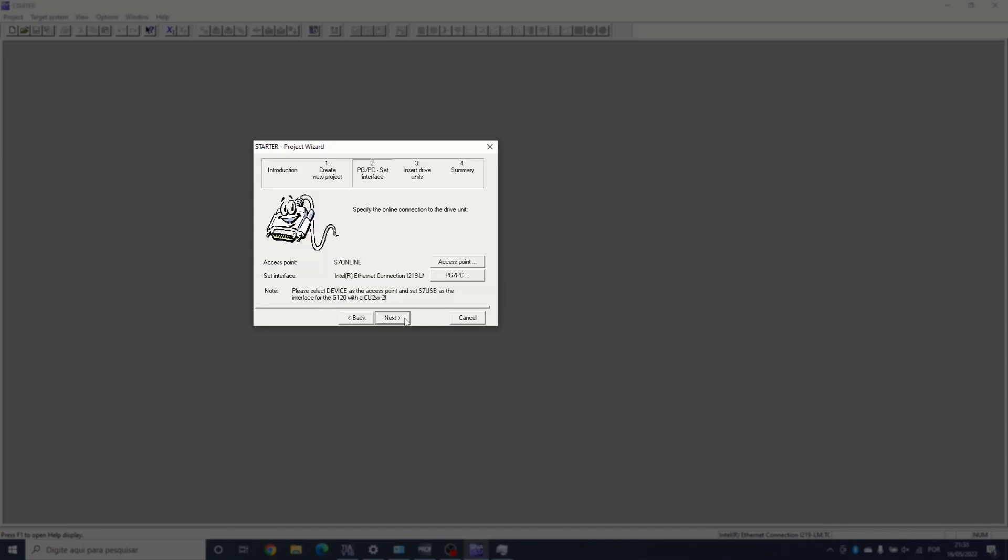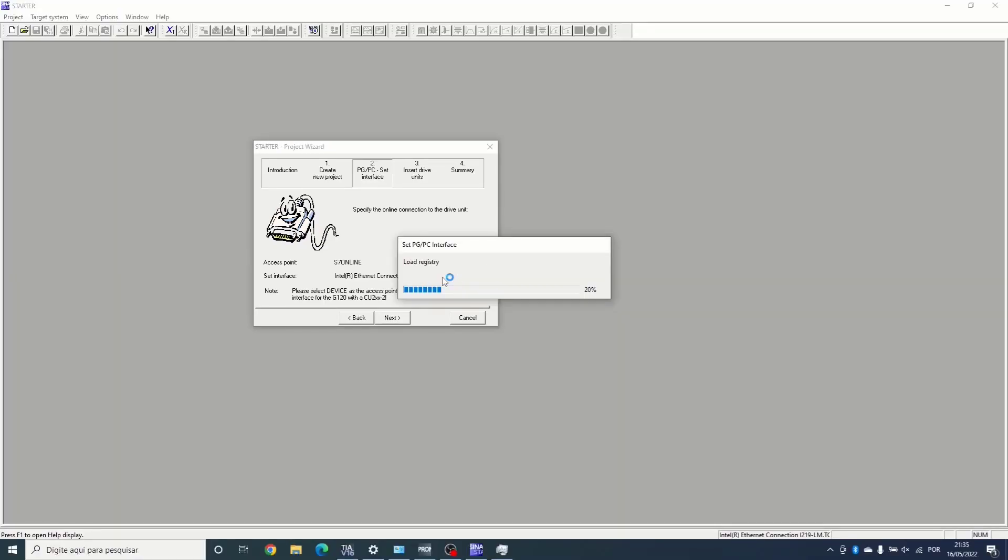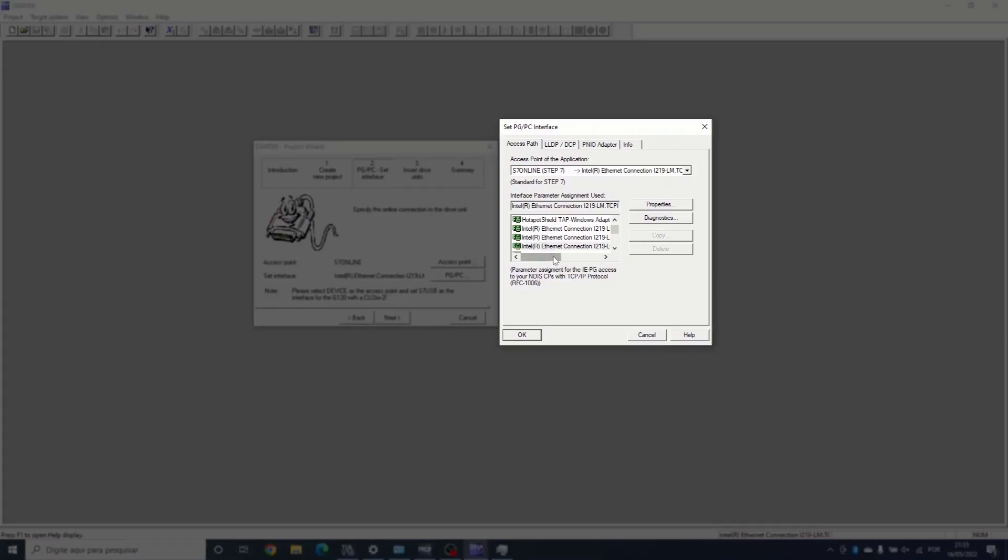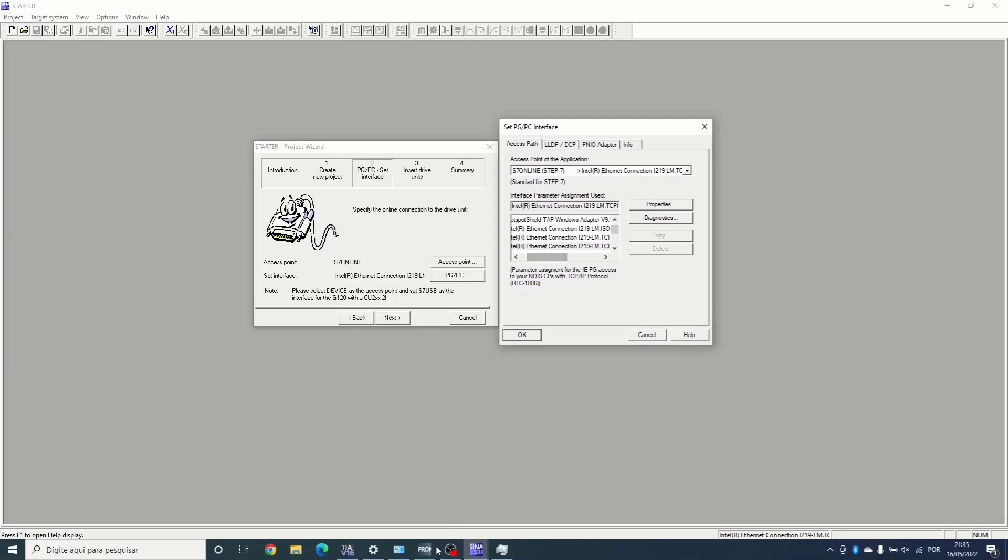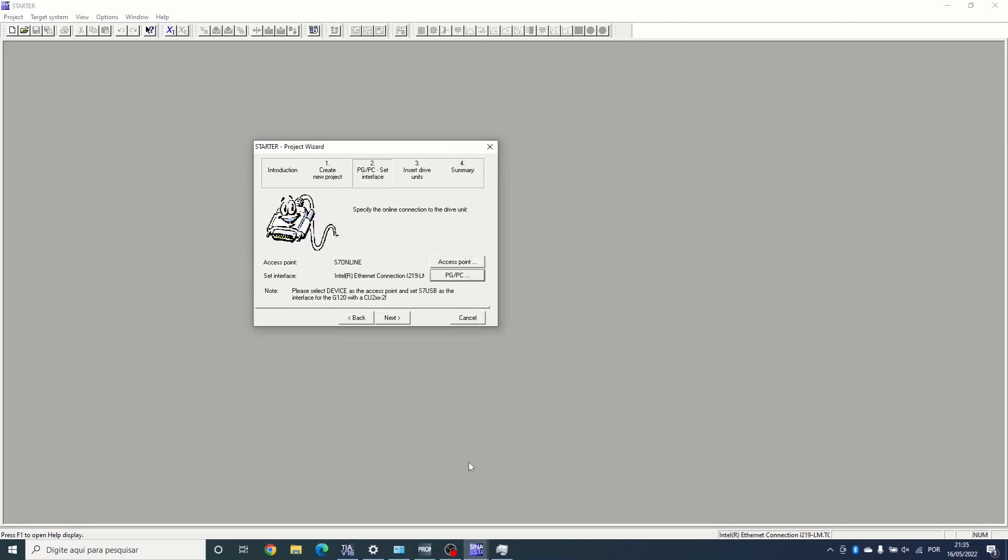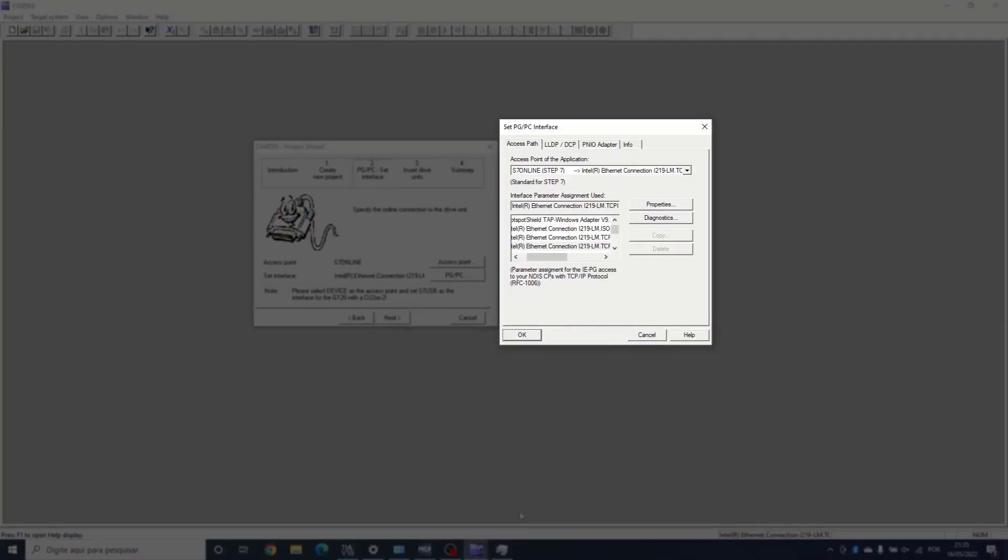It's important to set the correct PG/PC interface, which is the communication driver you use to find the drive unit. Since we're done in ProfiNet, we're already in the same subnet network and we have to select our network adapter as our communication driver.